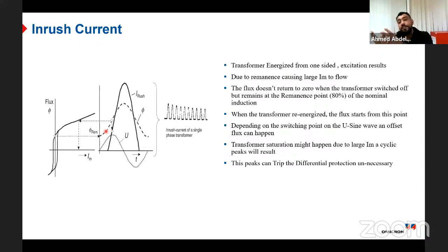The inrush is a very transient current, consisting of current peaks, as you can see here, and these peaks are mainly second harmonic. When they analyzed the current during the inrush condition, they found it is mainly second harmonic content, because it decays very fast and is like peaks. If I don't take this current into consideration when energizing the transformer, the inrush current can mislead the relay, and the relay can consider it a differential current, because it is current flowing from one side and not flowing on the other side. So the relay will trip. So every time I energize the transformer, it trips because of the inrush current.